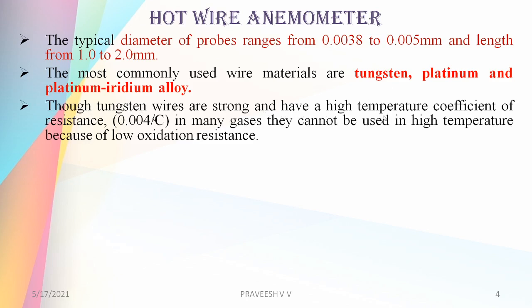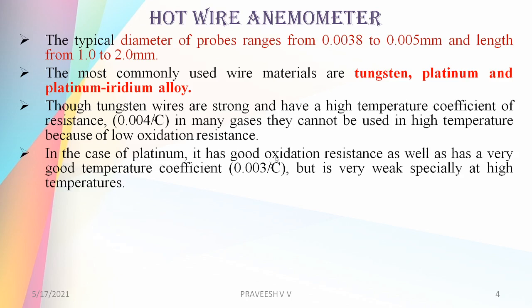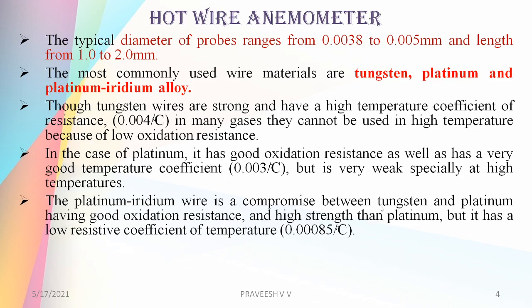Tungsten wires are strong and have a high temperature coefficient of resistance of 0.004 per degree Celsius. However, in many gases they cannot be used at high temperatures because of low oxidation resistance. Platinum has a temperature coefficient of resistance of 0.003 per degree Celsius, but it is very weak, especially at high temperatures, though its oxidation resistance is good. Platinum-iridium wires are a compromise between tungsten and platinum, having good oxidation resistance and higher strength than platinum.